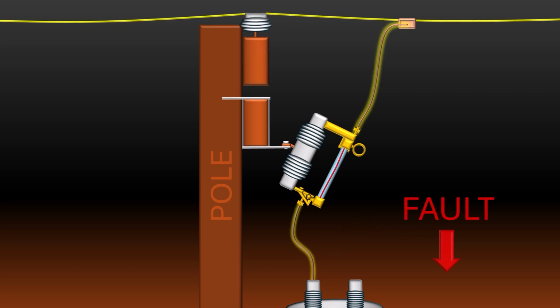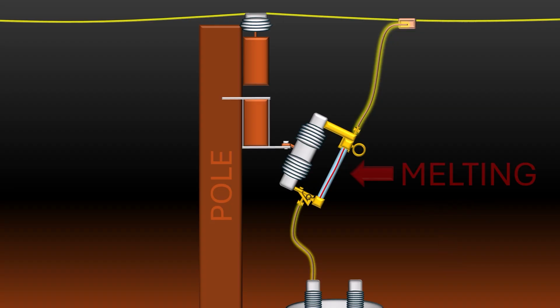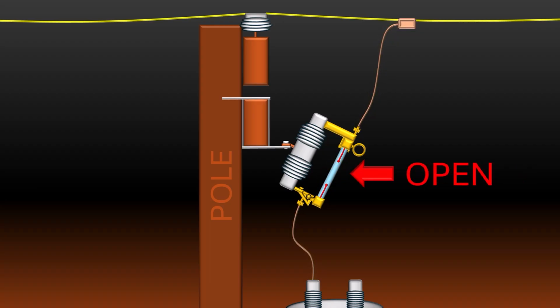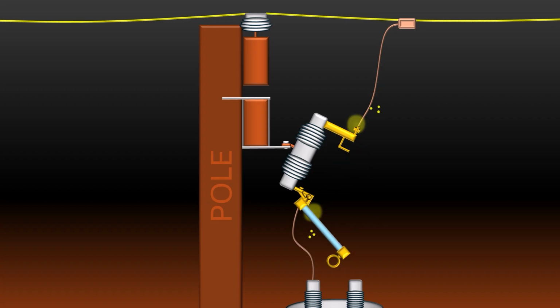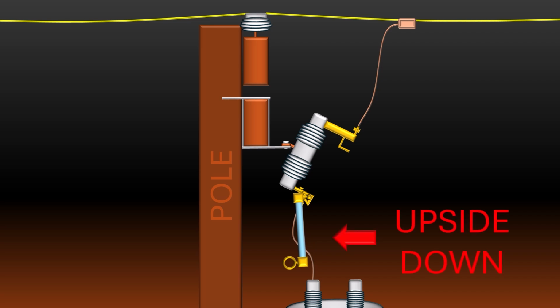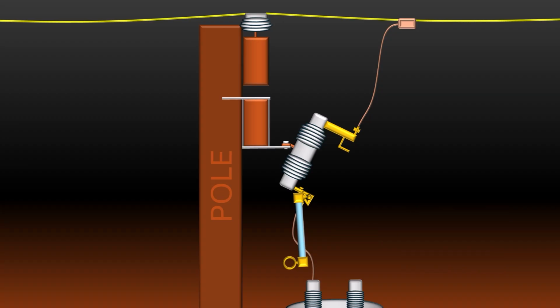In the event of a fault on the transformer side of the cutout, the excess current caused by the fault will cause the fuse element to melt. This will open the electrical connection and de-energize the transformer. This usually happens with a loud pop, which will cause the fuse holder to kick itself off of the cutout. The fuse holder, now hanging in the upside-down position, aids the line worker by providing a visual cue regarding the location of the fault so they can begin the process of restoring the now de-energized service.